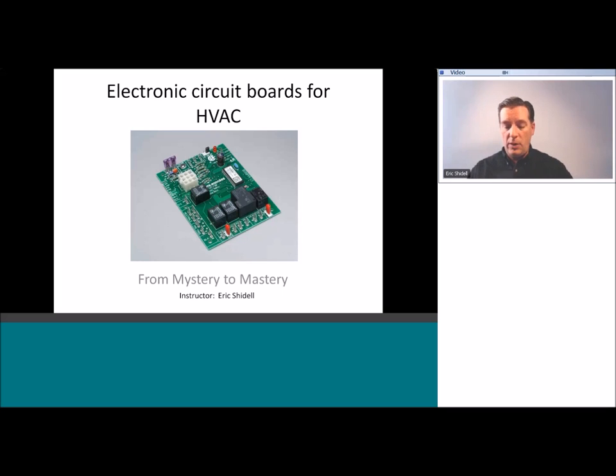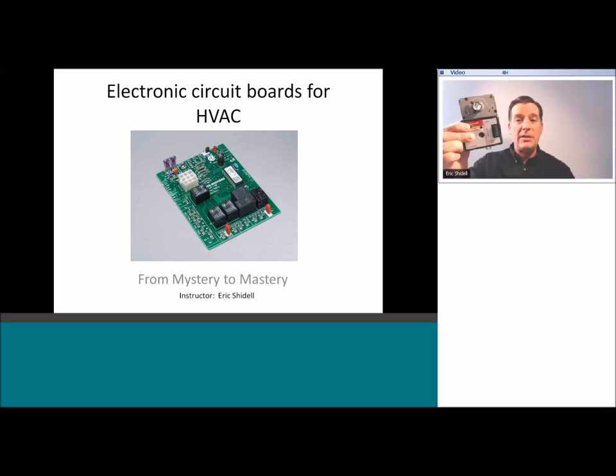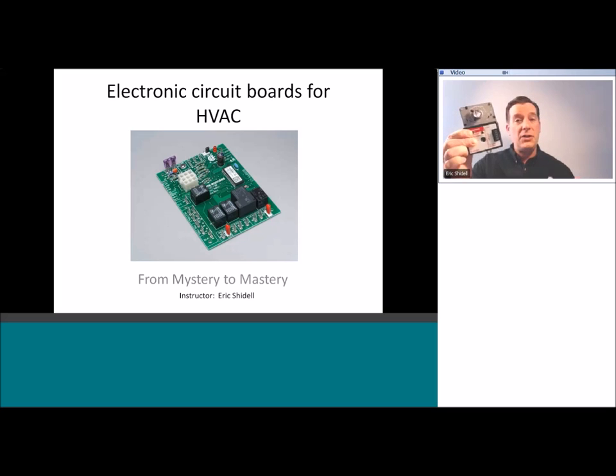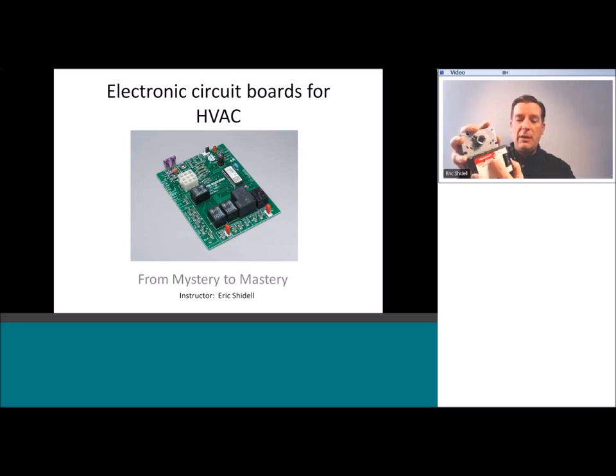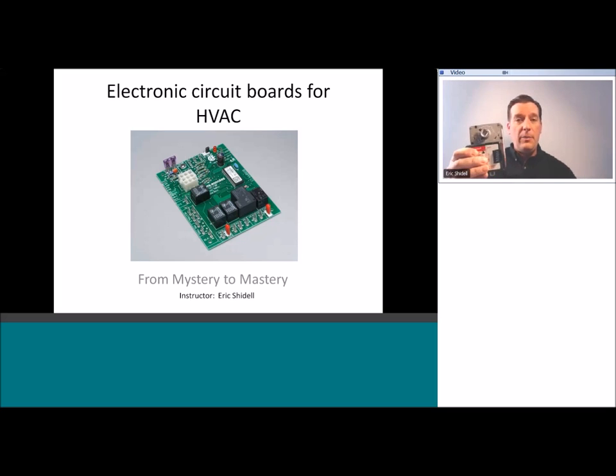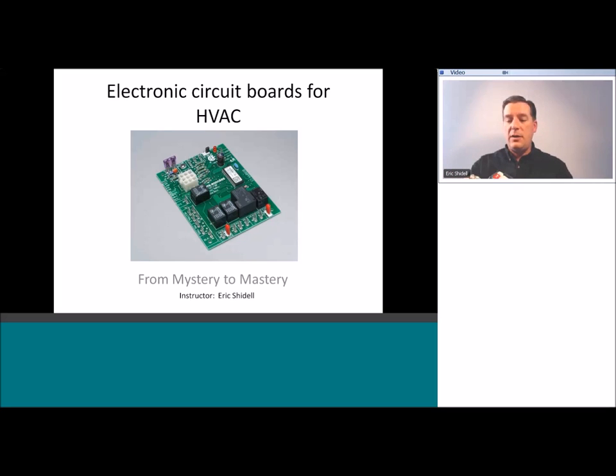Here I've got a Honeywell damper actuator. The job of this little fellow is multifold, and this is one of the keys to understanding how to troubleshoot things with electronic circuit boards. This thing has an electronic circuit board mounted inside of it that operates the whole thing. Its job is to position the damper in the correct location upon demand and provide feedback telling what position the damper is in. There's lots of sophistication in this device, dating back to circa 2007.